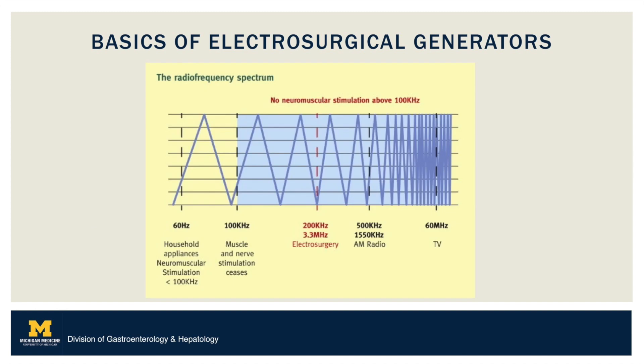The frequency at which the alternating current is run dictates the effect on the tissue. Typical frequencies for endoscopic electrosurgical generators are between 200 kilohertz and 3.3 megahertz. Frequencies below 100 kilohertz cause neuromuscular stimulation and are well below what is used in endoscopy.